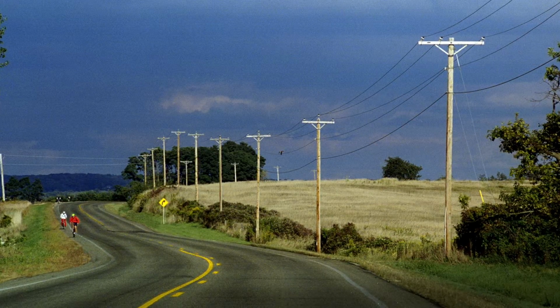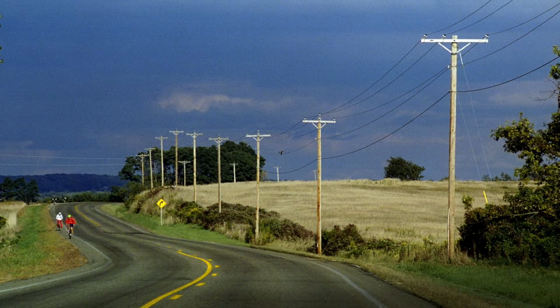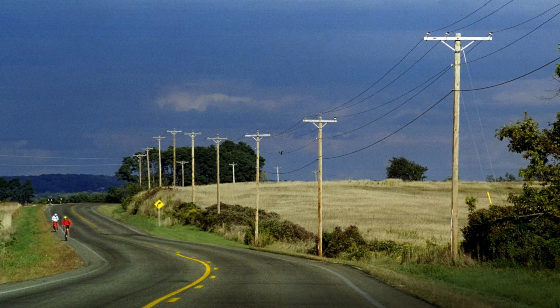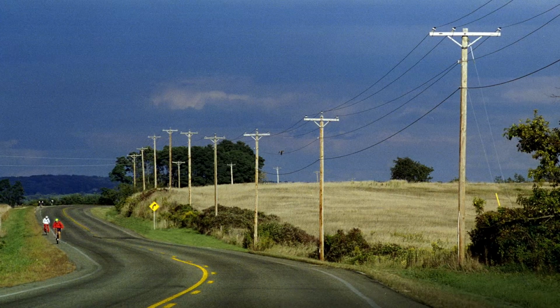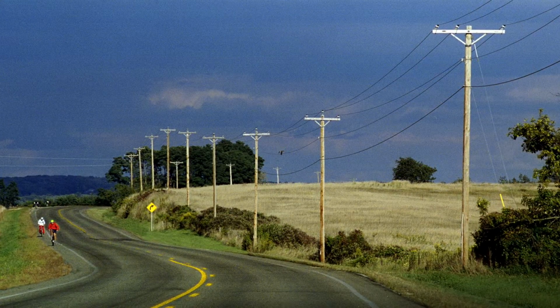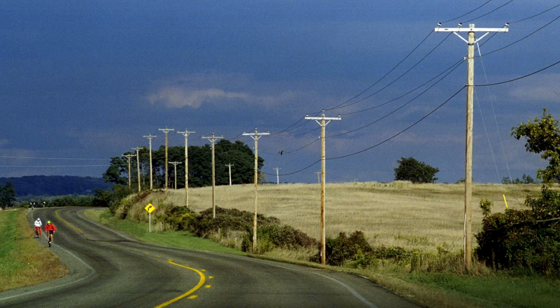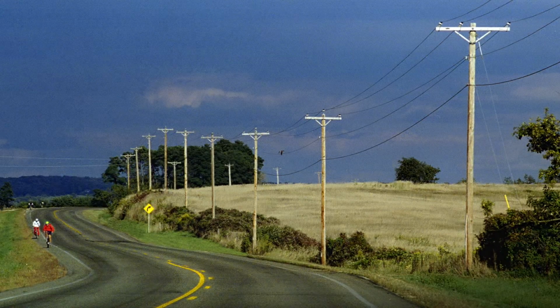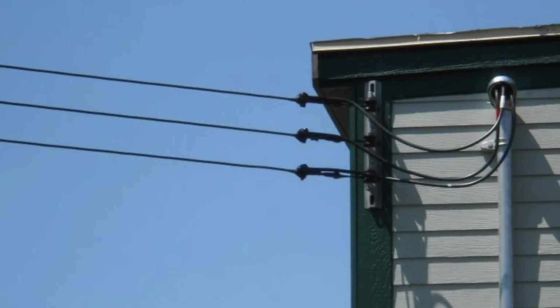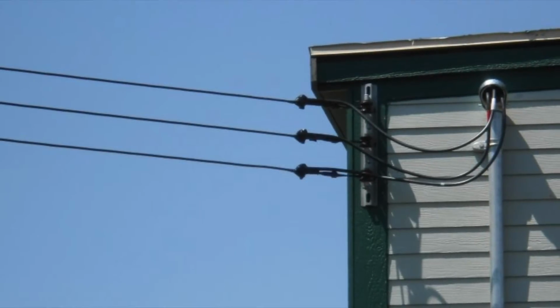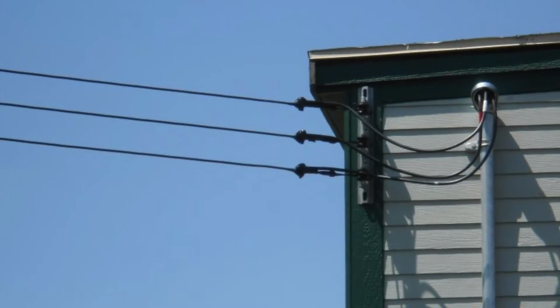The electric potential at this point is approximately 15,000 to 20,000 volts. Finally, the electricity passes through a final step-down transformer that brings the electricity to a safe voltage between 240 and 120 volts. A service drop wire then connects a house or building's power meter to the source. Once the electricity reaches this point, the house or building will be able to freely use electricity.